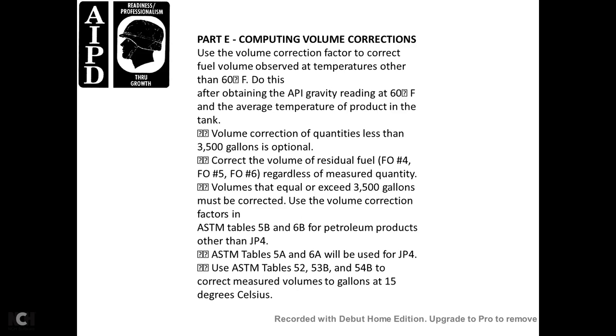Part E: Computing the volume correction. The volume correction factor for fuel volume is referenced to 60 degrees Fahrenheit. Obtain the API gravity reading at 60 degrees Fahrenheit and the temperature for the product in the tank volume. Correction is optional for quantities of less than 3,500 gallons, but residual fuel must be corrected regardless. Regardless, when the measured quantity equals or exceeds 3,500 gallons, volume correction factors from ASTM tables 5B and 6B must be used.